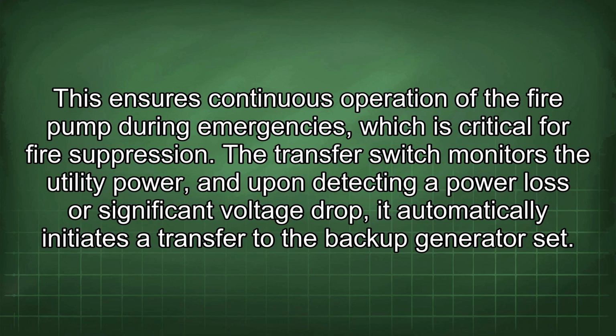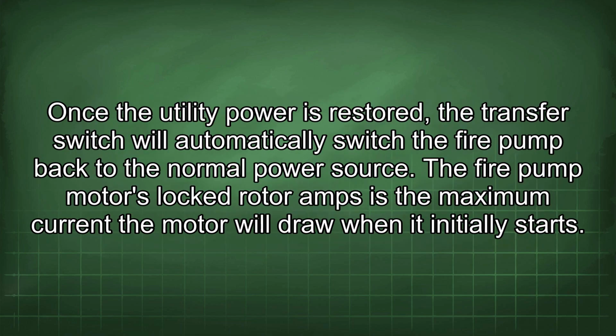The transfer switch monitors the utility power, and upon detecting a power loss or significant voltage drop, it automatically initiates a transfer to the backup generator set. Once the utility power is restored, the transfer switch will automatically switch the fire pump back to the normal power source. The fire pump motor's locked rotor amps is the maximum current the motor will draw when it initially starts.